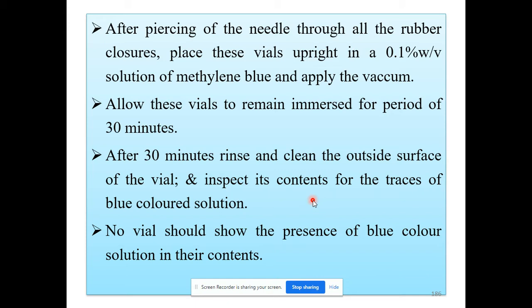If the rubber closure is not having self-sealing ability, the methylene blue solution will enter inside the vial and the water content of that vial will turn blue. No vial should show the presence of the blue color solution in their content — not a single vial. If no vial shows blue color in its contents, it indicates that the rubber closure has good self-sealability and passes the test.